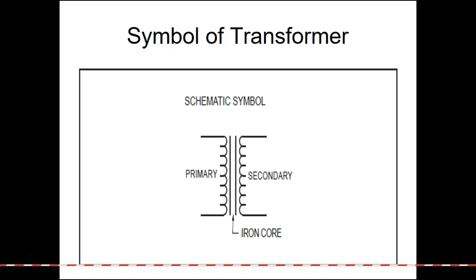So this is the symbol of a transformer. This would be a single winding transformer. So we have the primary. All your primaries are going to point toward the source of the power. And then we have our secondaries, which always point toward the load. Even if you go from transformer to transformer, like in the power grid, you go from substation, you might drop it down for safety, but then you can run into another substation and step it up and send it.